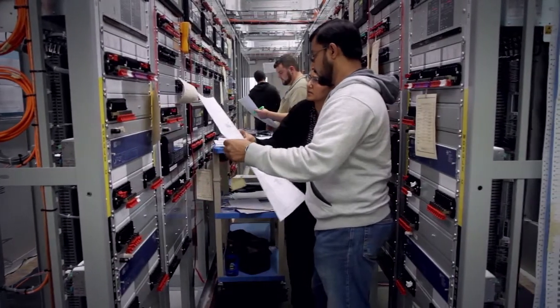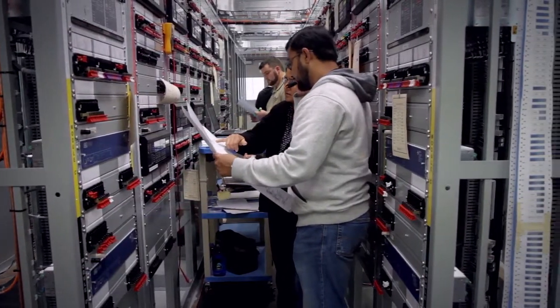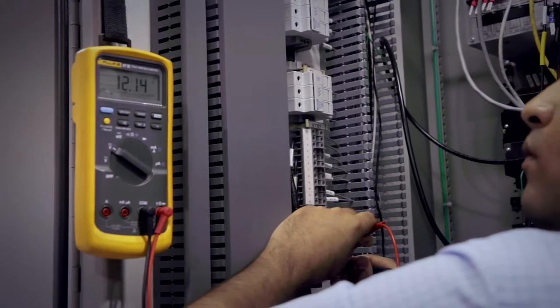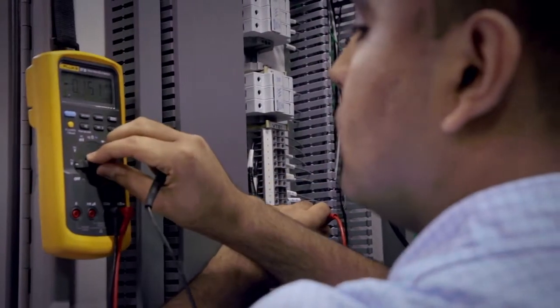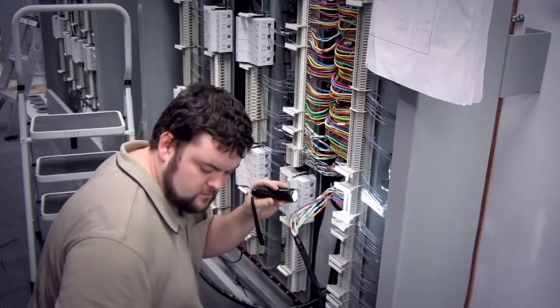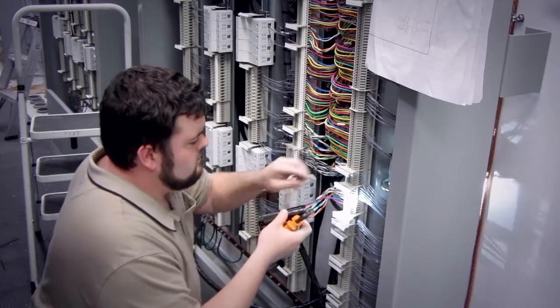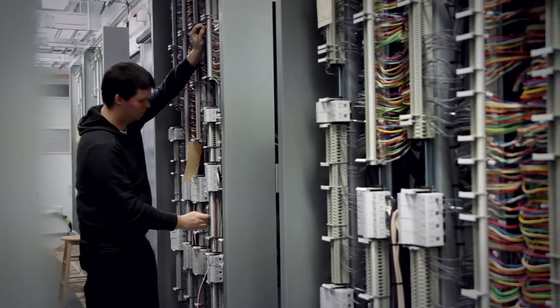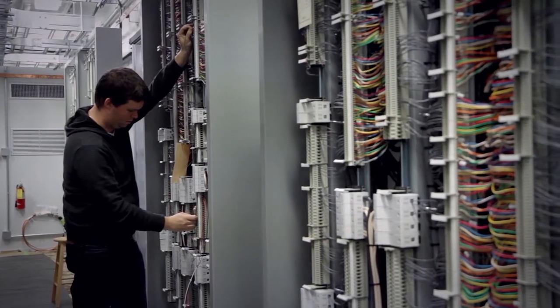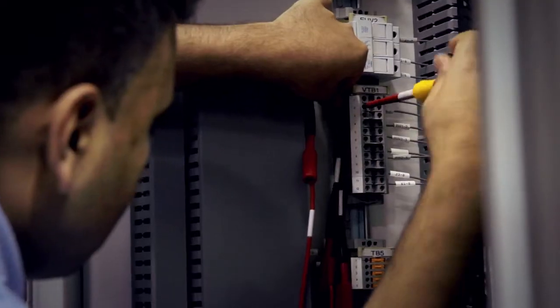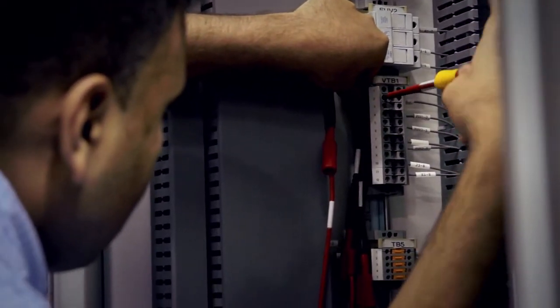As standard, all Virelec work first goes through physical assembly and wiring testing. Typically, the panel components are inspected and checked for correct location and installation against the layout drawings. Then the electrical schematic diagrams are used to perform point-to-point wiring checks. All wiring connections are documented as being correct on the test drawings by highlighting in a green marker. Following wiring checks, the work then proceeds into live tests.